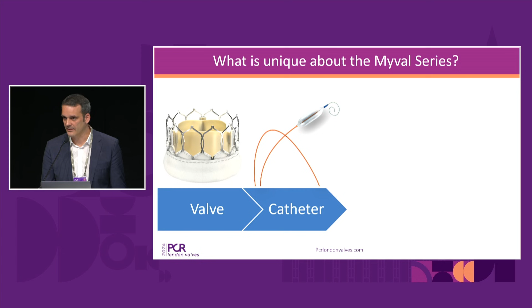The next important part of the system is the catheter, of course, and the catheter is different to others. The genius idea, in my opinion, is to have these two cone-shaped plastic cones within the balloon, which the company calls stoppers, which allow you to simply crimp the valve on the device. This is something we never talk about, but in my opinion, the ease of crimping is important. I can crimp it myself. This is the only device where I managed to crimp it myself, so I can use it at night as a bailout option whenever needed.